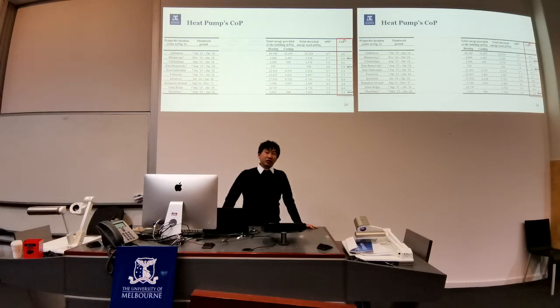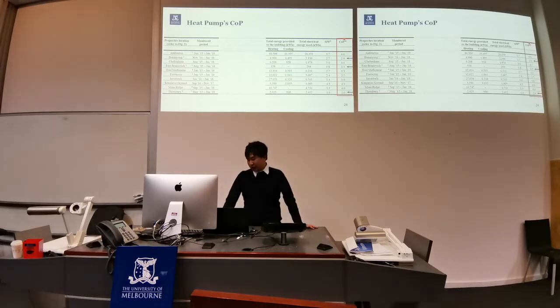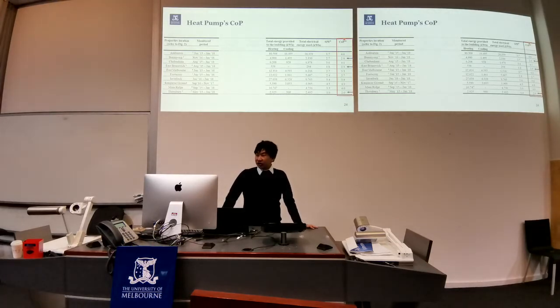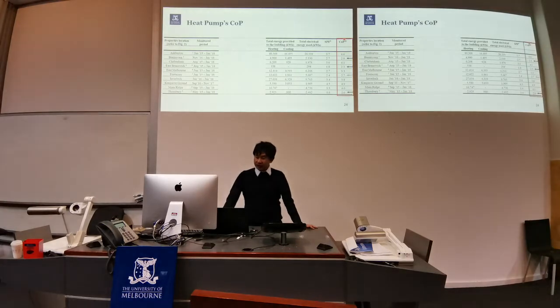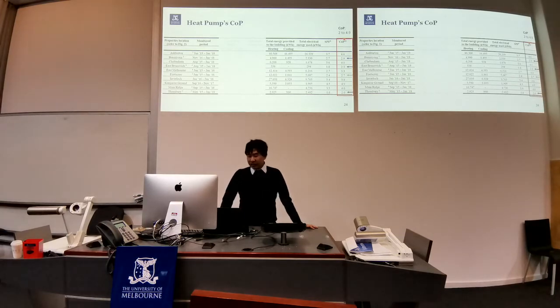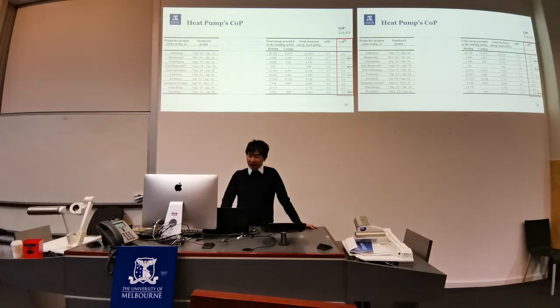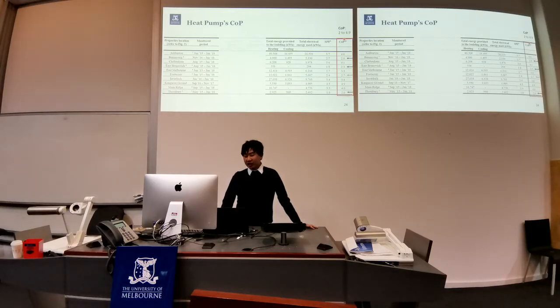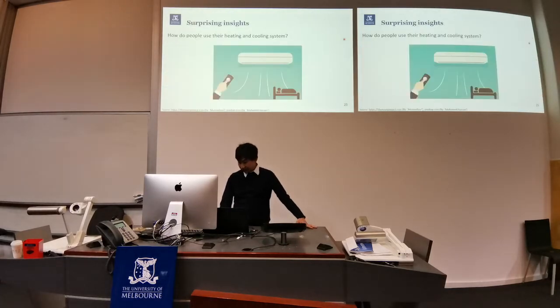Unfortunately, it turned out that it did not perform as well as expected due to the limited amount of research and development that has been put into this heat pump. Although it was not known at the design stage, this property ended up severely under design. Despite that, all the COPs that we measured are between 2 to 4.9, which is in line with COPs measured from other experiments around the world.